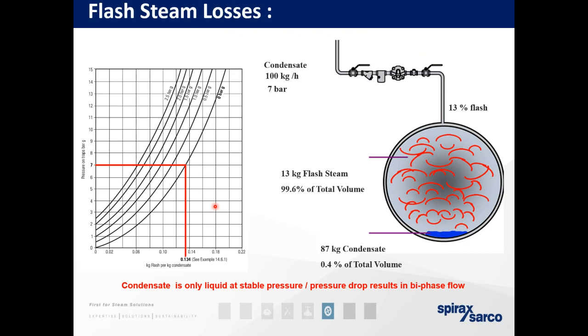As it says at the bottom here, condensate is the only liquid at stable pressure. Because of the pressure-temperature relation at 7 bar, if we heat it past that point, we'll produce steam. But at 7 bar temperature, it's both steam and condensate at the same time. That's what we call the biphase.